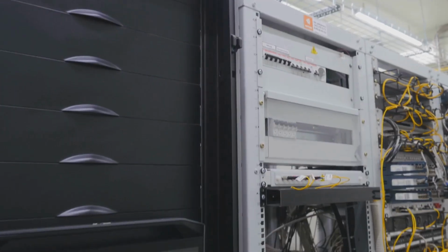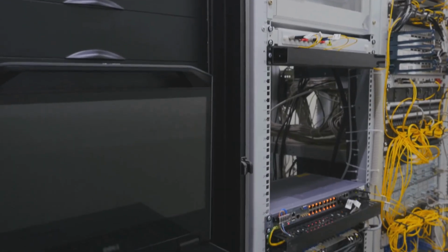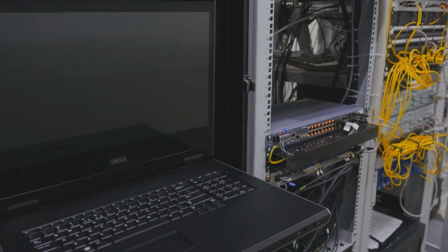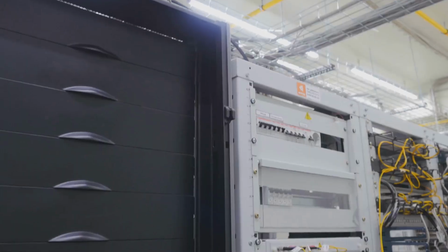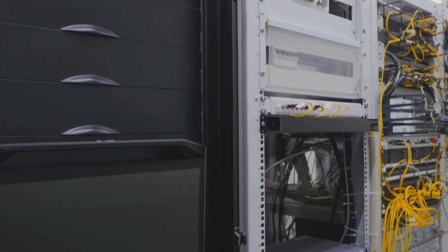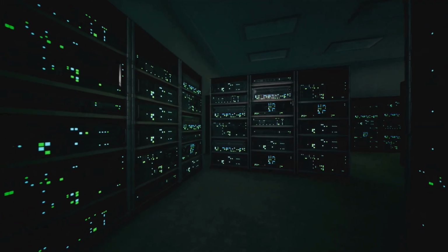Many data centers use hot aisles and cold aisles. Cold air is delivered to the front of servers. The servers pull that air through the equipment. Hot air exits from the back. By organizing server racks this way, engineers keep hot air and cold air separated, which makes cooling more efficient.